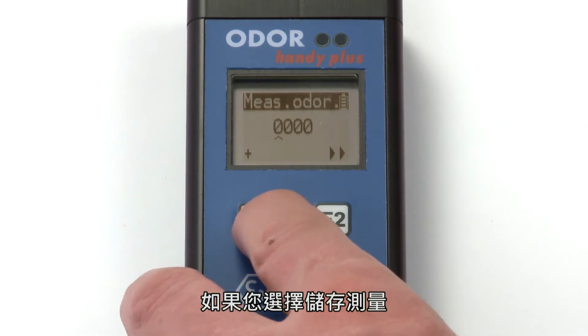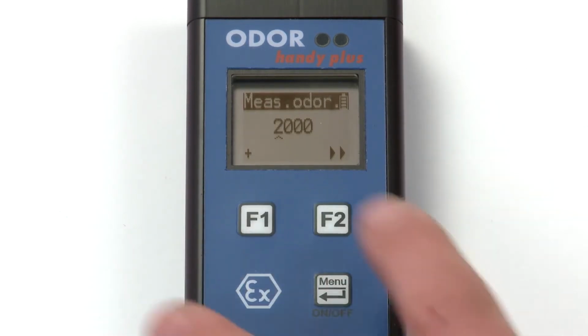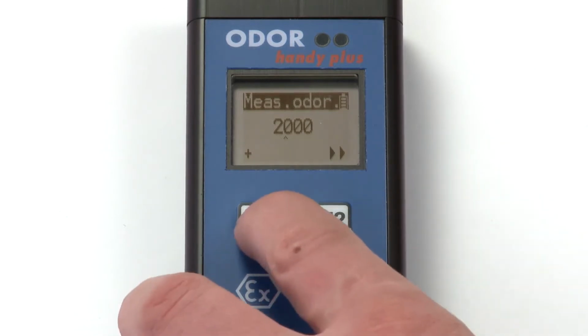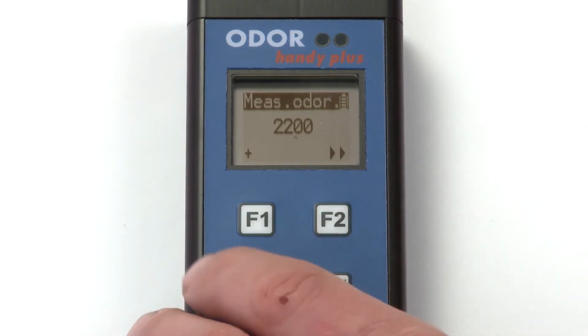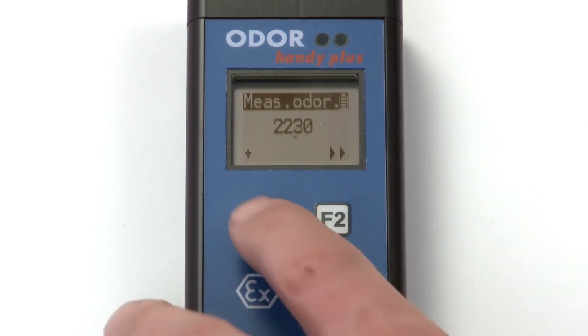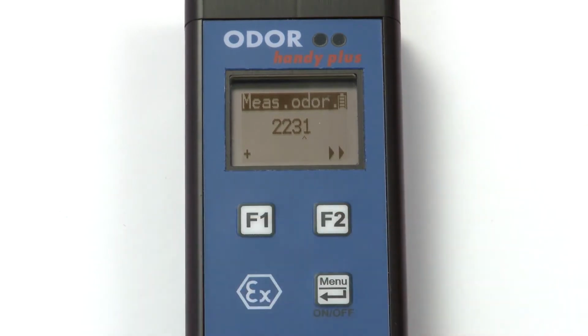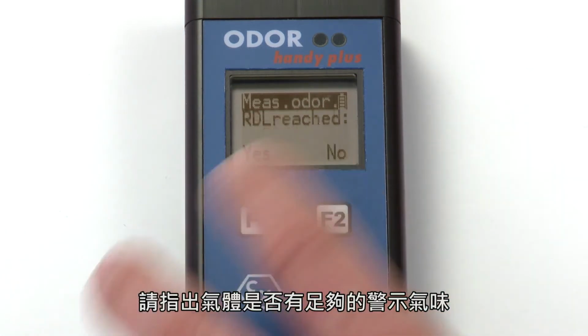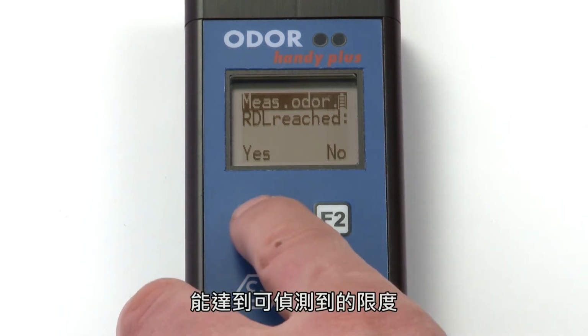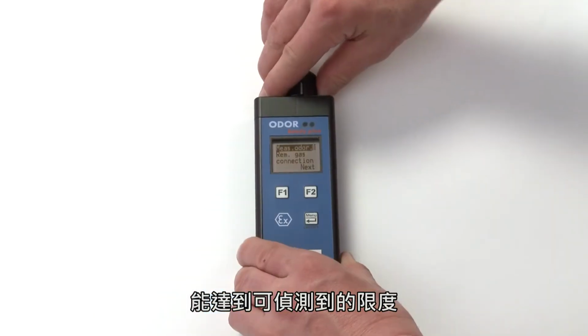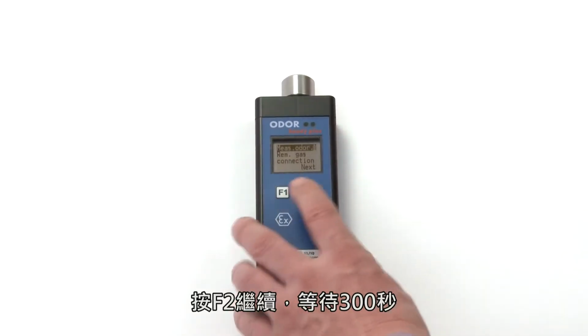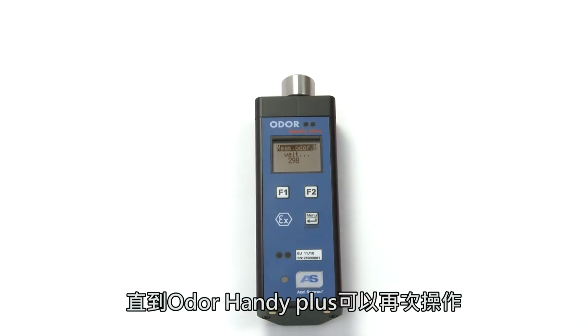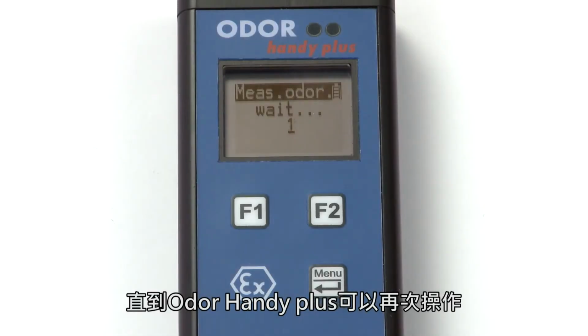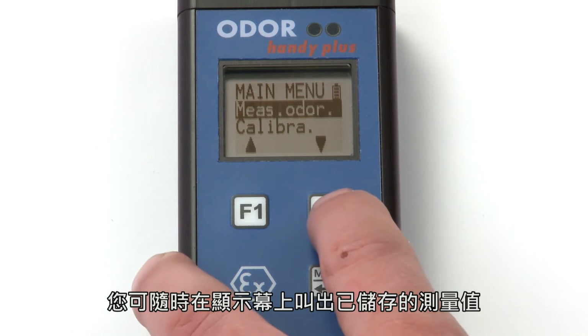If you choose to save the measurement, you will need to enter your measuring point number. Press Enter to continue. Press F2 to continue. Please indicate whether the gas had a sufficient warning odor, respectively reached the readily detectable limit, RDL. Remove the sample gas. Press F2 to continue and wait 300 seconds until Odor Handy Plus is ready for operation again. You can retrieve saved measurement values on the display at any time.